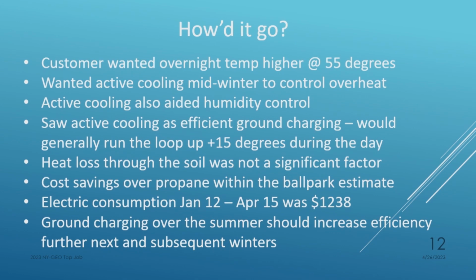So as it goes with creeping requirements, they said, well, give us 55 degrees. And if you put another one in, give us 60 degrees. So I don't know how that's going to work out next time, but 55 worked out fine. Helped with humidity control. Heat loss through the soil was not a significant factor. Electric consumption, when the system was commissioned January 12th through the end of the growing season, was only $1,238, which saved them probably $5,000, $6,000. So it's quite a bit. And we expect that ground charging is going to help us out in years to come.